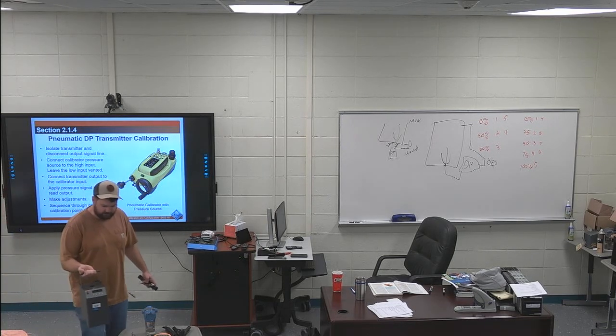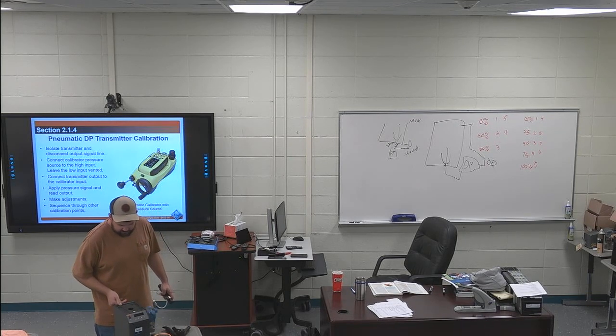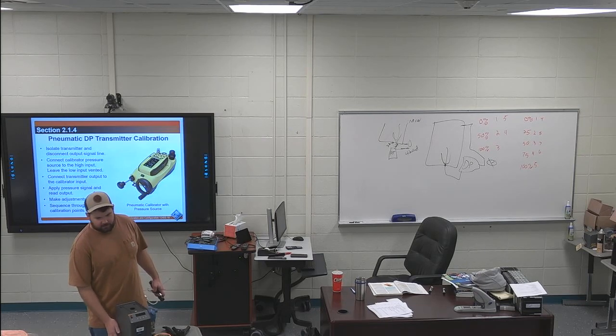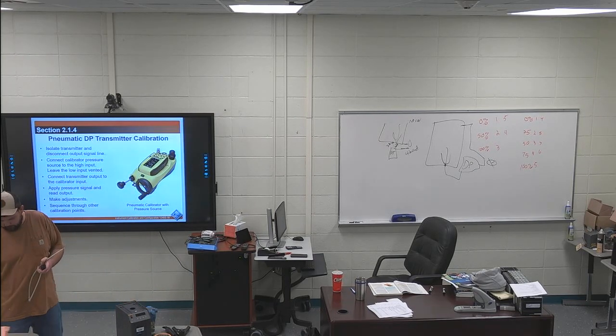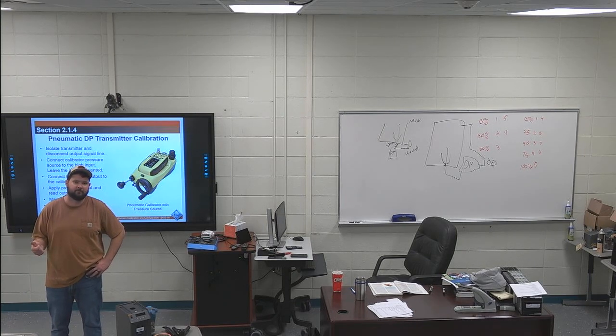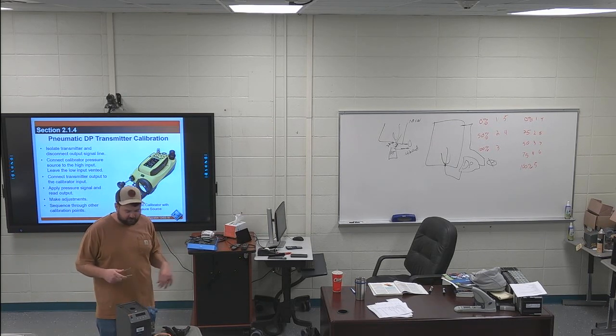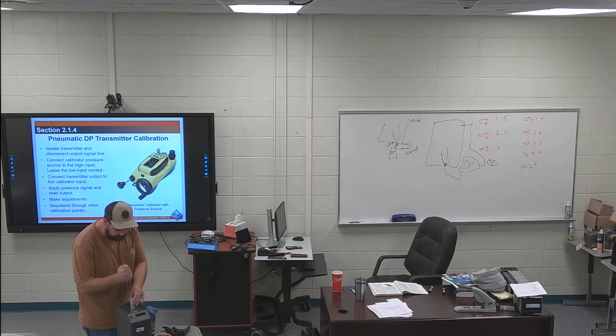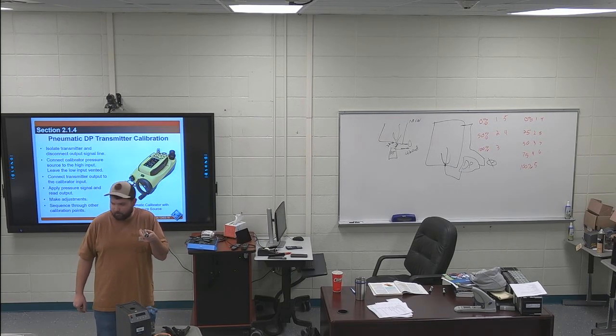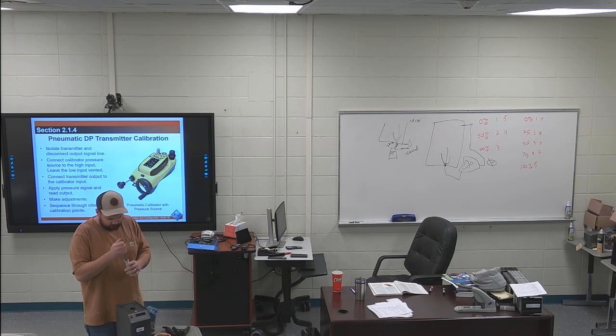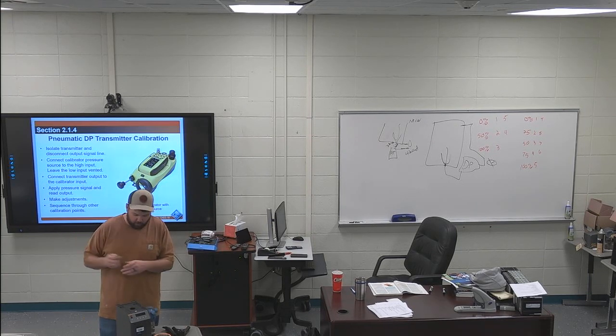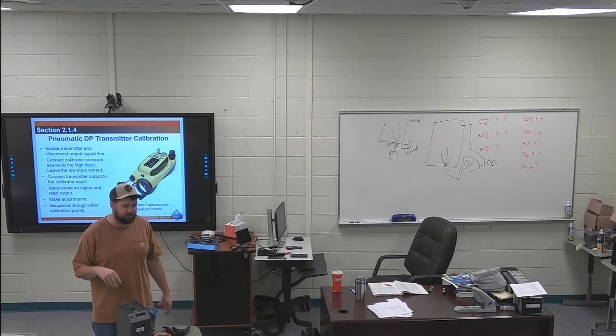Temperature is used in a ton of different places. I saw that, I was wondering what that was. So this is a dry well calibrator. Where does the thermocouple go inside of that protects it from the process? What's that called? Thermowell. So you have thermowells that are different sizes, right? This has a little sleeve, and they have different size holes for different size thermowells. So literally, you just pull your temperature probe out of there, stick it in this thing, turn this on, and you can set it to a very, very specific temperature.